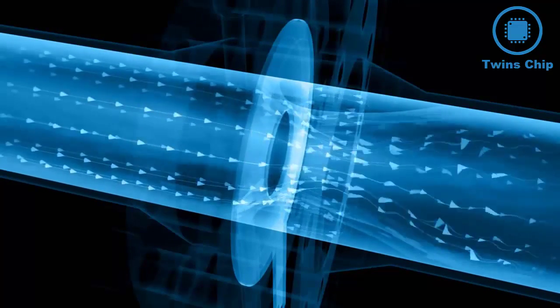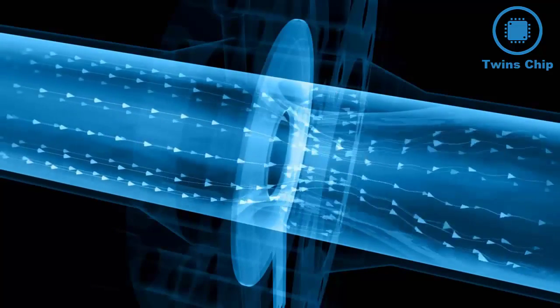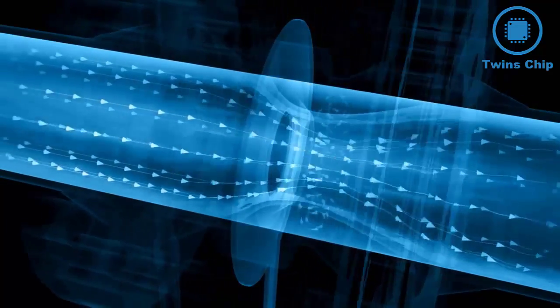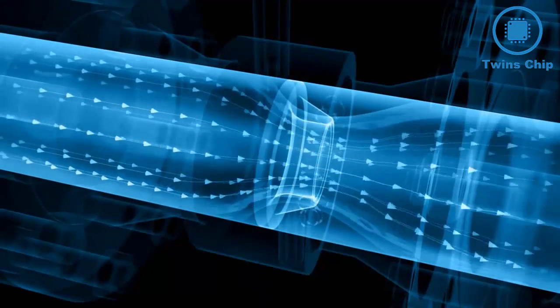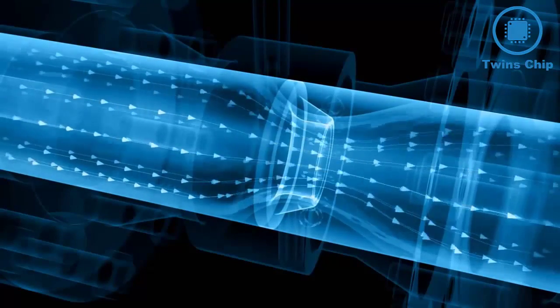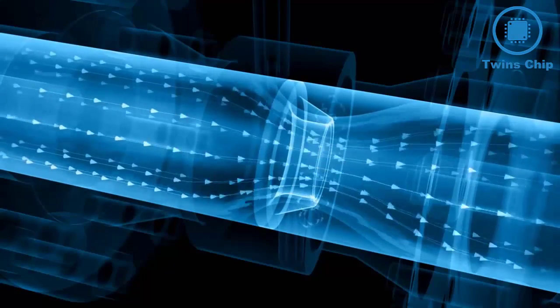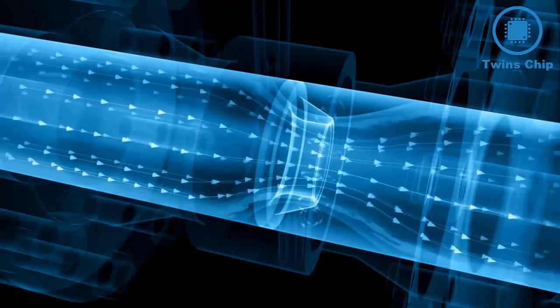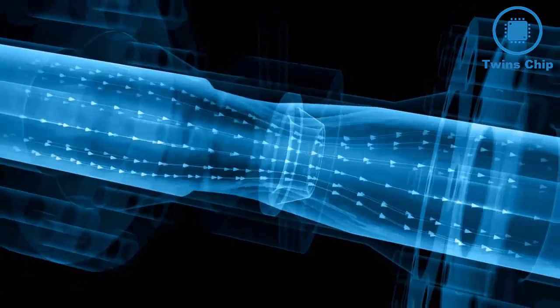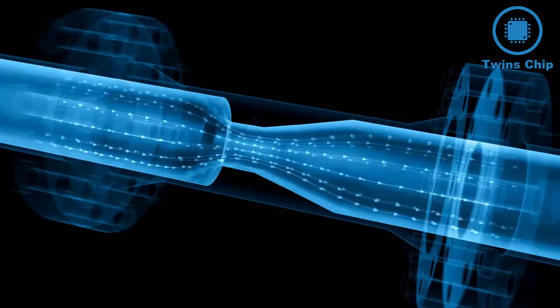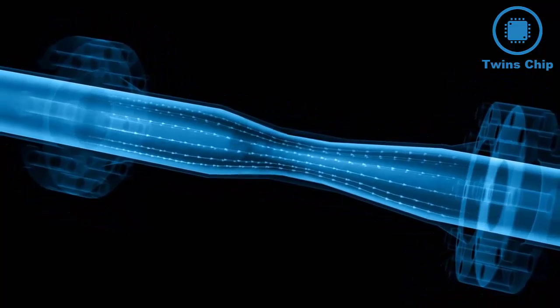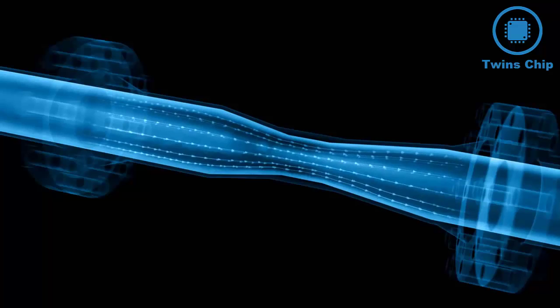This demonstration shows that an abrupt restriction generates severe turbulence in a fluid. Nozzles with a rounded, funnel-like inlet clearly reduce turbulence and thus create less pressure loss. Nozzles are particularly suitable to higher flow velocities or to fluids with abrasive solid particles. Turbulence reduction is even greater with Venturi nozzles. And finally with Venturi tubes, where the restriction is created by longer conical constrictions in the pipe wall.